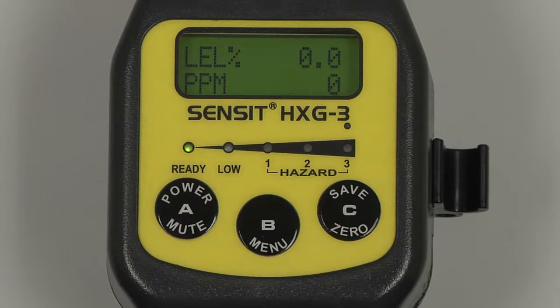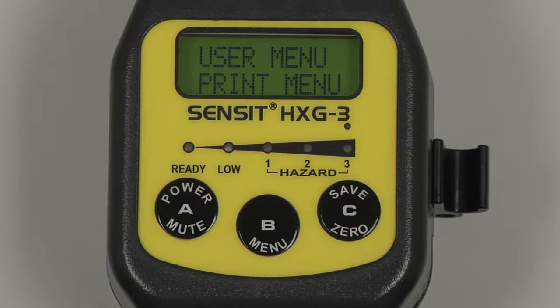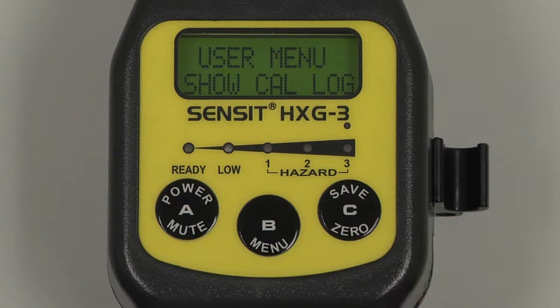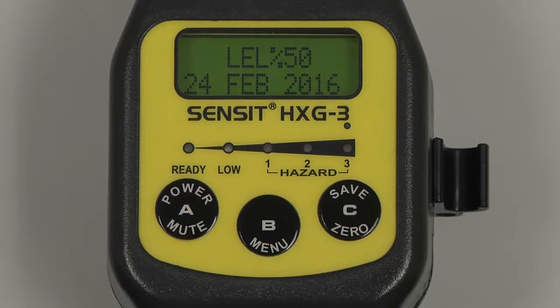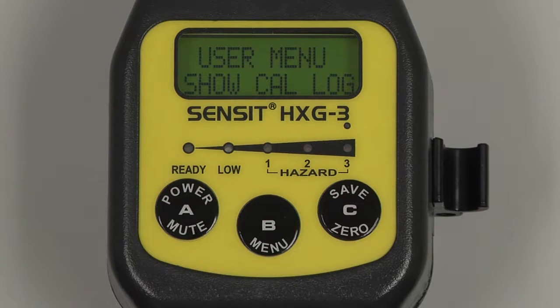To verify the calibration date, enter into the user menu by pressing and holding the B button, and scroll through the menu by pressing and releasing the C button, until Show Cal Log appears. Select by pressing and releasing the B button, and we'll have a display for the calibration point and the most recent date that the instrument was calibrated. Pressing and releasing the B button will return to the user menu, and we can return to the working display by pressing and releasing the A button.